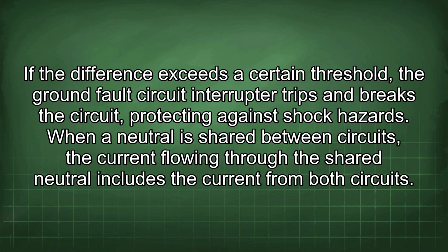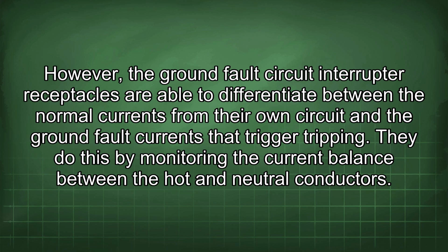When a neutral is shared between circuits, the current flowing through the shared neutral includes the current from both circuits. However, the ground fault circuit interrupter receptacles are able to differentiate between the normal currents from their own circuit and the ground fault currents that trigger tripping. They do this by monitoring the current balance between the hot and neutral conductors.